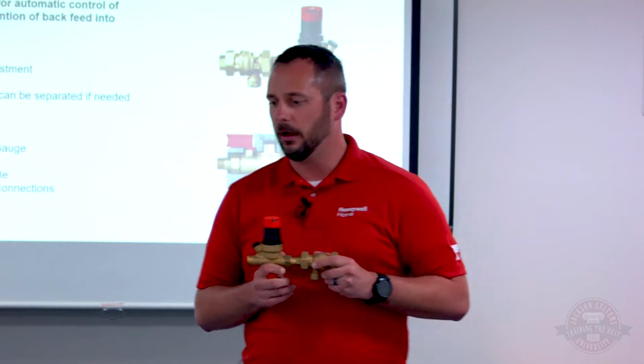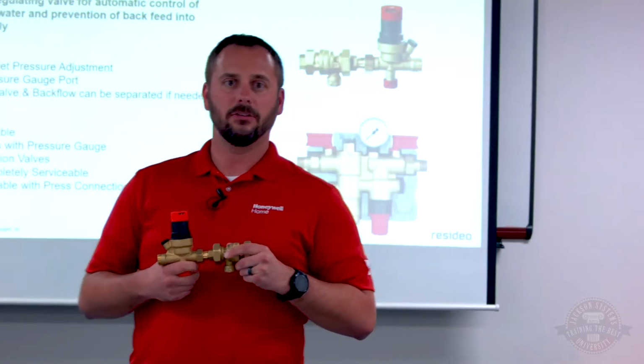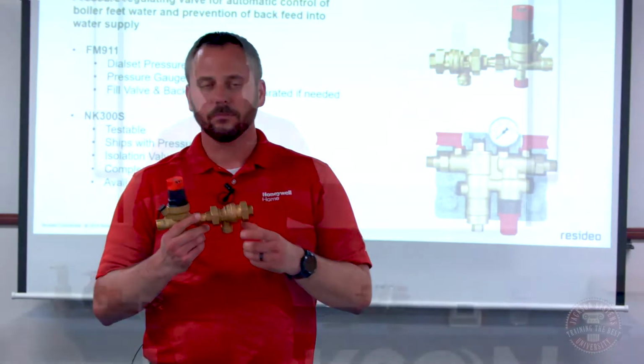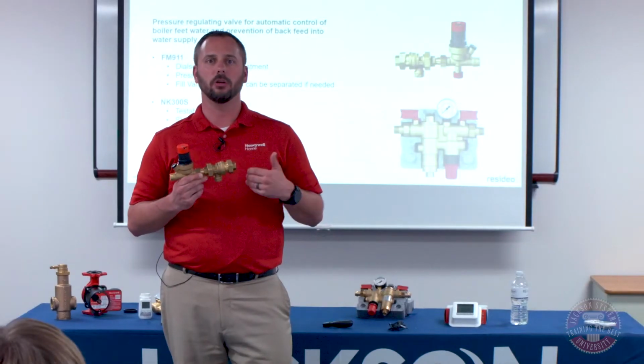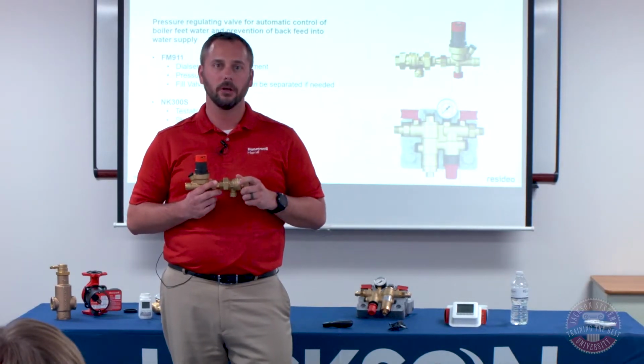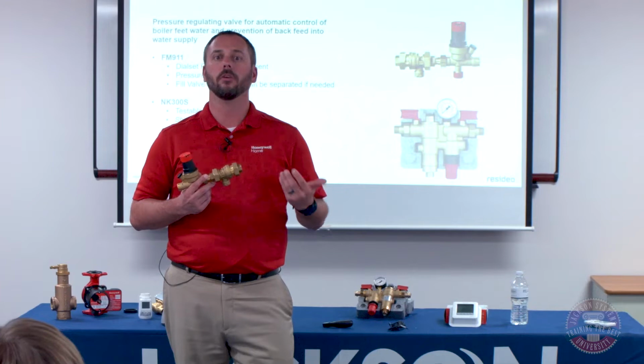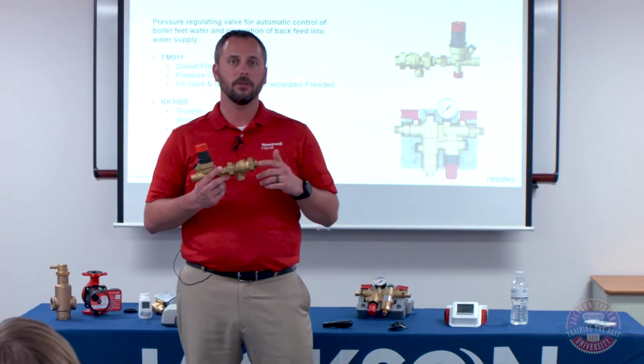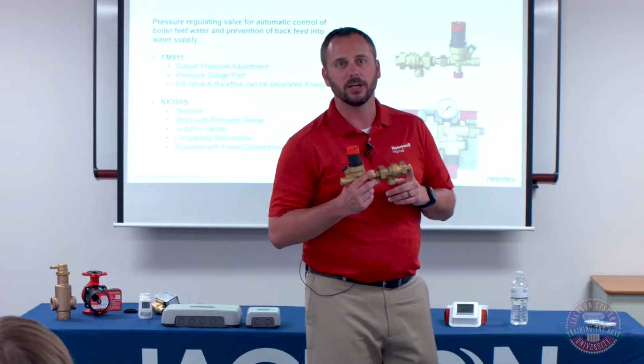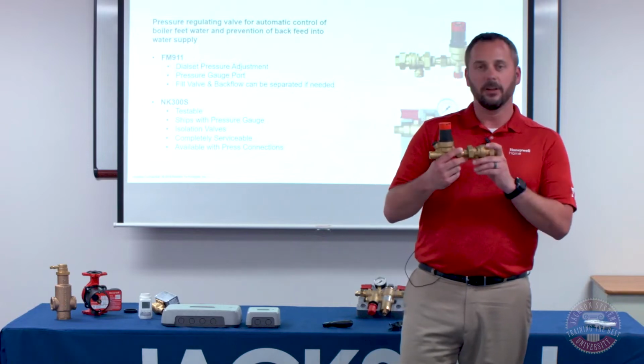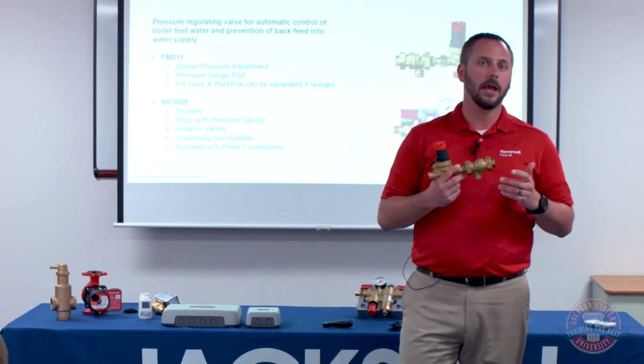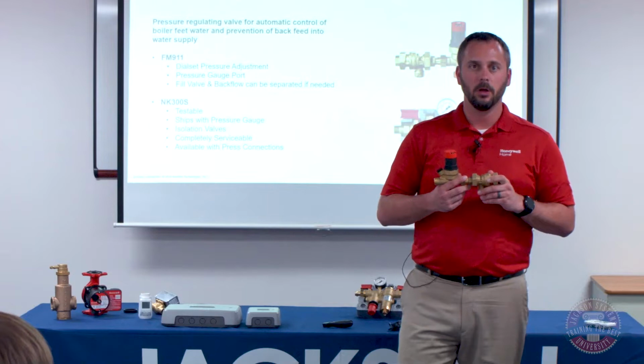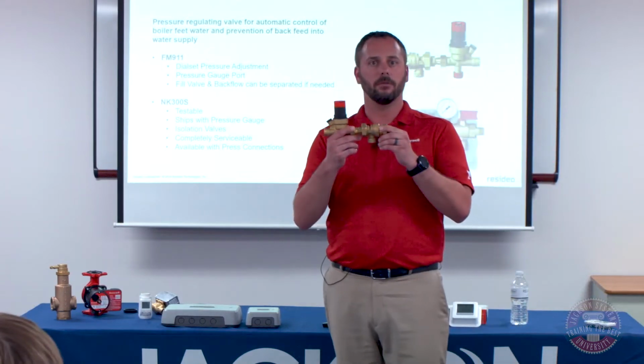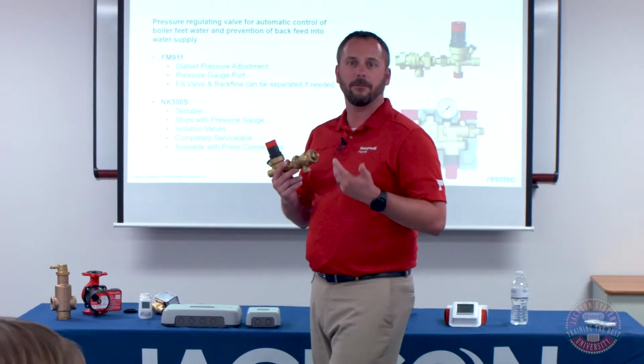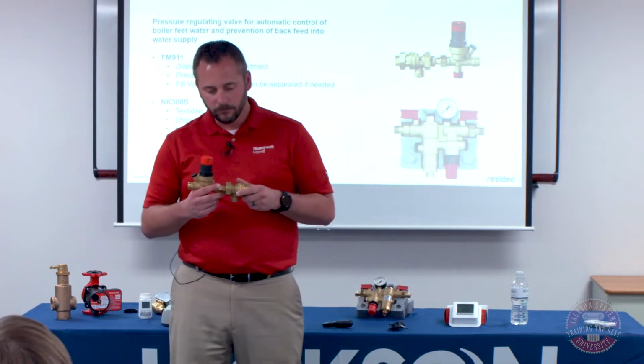What I've seen happen a lot of times is, I guess you could say, eventually major problems where you're masking an issue. Could be a nail that the drywaller hit in some tubing that erodes over time. You end up with a small leak. This will continue to keep your system pressurized at, in this instance, 15 psi. If you do that, you may be masking a bigger problem. So I always recommend shutting off your water makeup to the system after you've had it commissioned for a while.